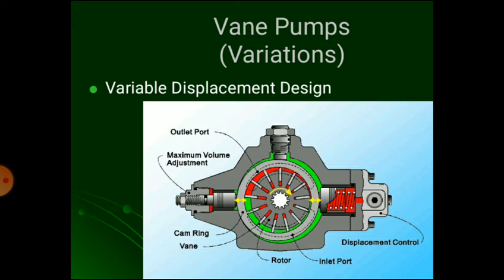In this type, it has two screws. One on the right hand is for pressure adjustment and on left hand side for setting eccentricity. By tightening pressure adjustment screw, the spring force on the casing is increased. This results in increase in discharge pressure of the pump.